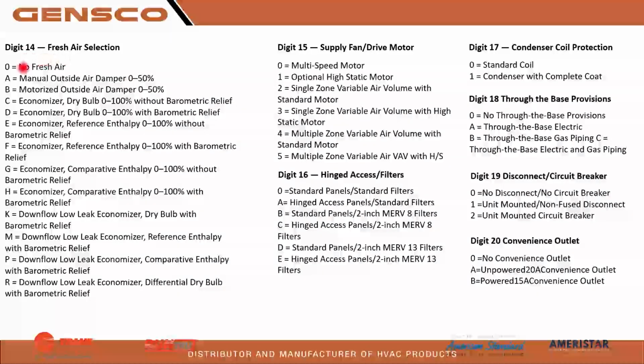Digit 14, this is one I always pay attention to because once I put in your model and serial number, it gives me the long model number, and I go ahead and click on it, and it gives me the breakdown of what it was ordered with from the factory. So we're going to see a lot of dry bulb, downflow low leak economizer dry bulb Ks.